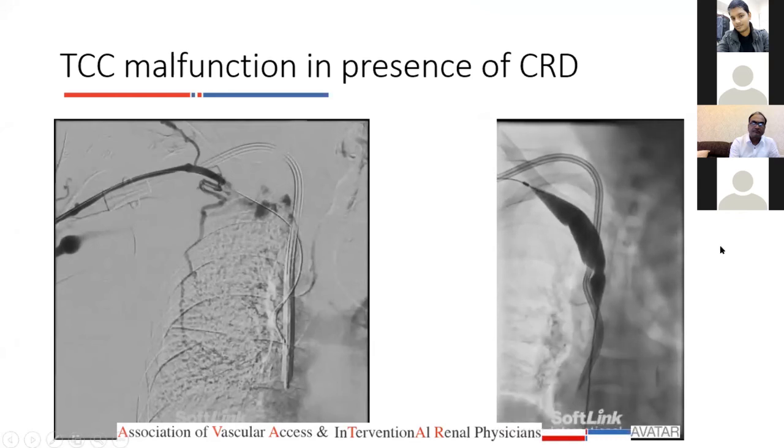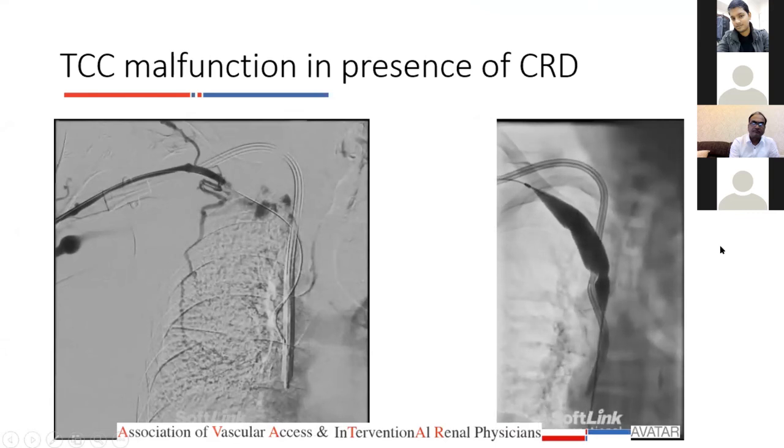You try hard and hard and hard, keep on pressing. You have an inflation device, so you know your rated burst pressure, that is the pressure up to which you can go safely, in which case 99% of the times the balloon would not rupture.